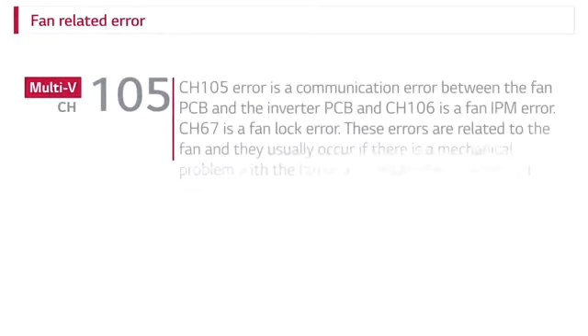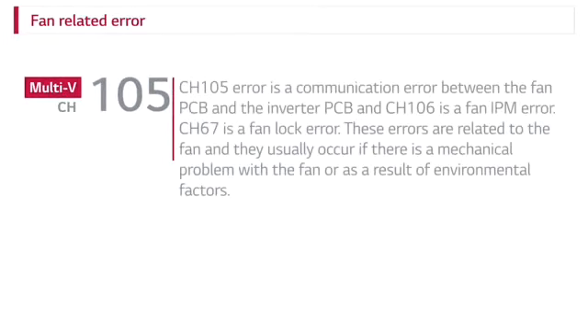Fan-related error. CH105 error is a communication error between the fan PCB and inverter PCB, and CH106 error is a fan IPM error. CH67 is a fan lock error. These errors are related to the fan, and they usually occur if there is a mechanical problem with the fan or as a result of environmental factors.